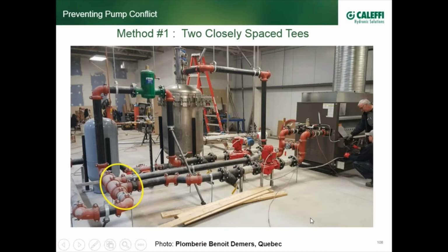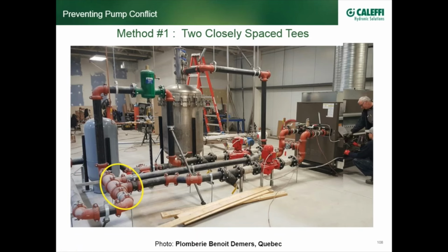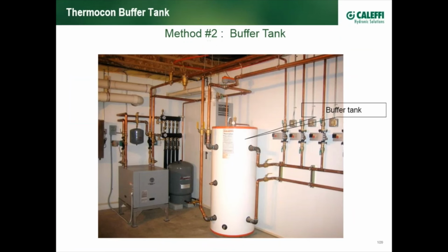And another job from Quebec, still being fabricated, of a primary loop, primary part to the boiler, and then a secondary. And here are your two T's connected together, closely spaced T's. Thanks, guys, for the photograph on that. Method number two, a buffer tank. Here's a buffer tank. On this job, it has multiple heat sources, a boiler and a heat pump over here. It is creating hydraulic separation.